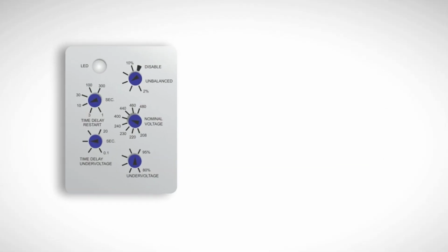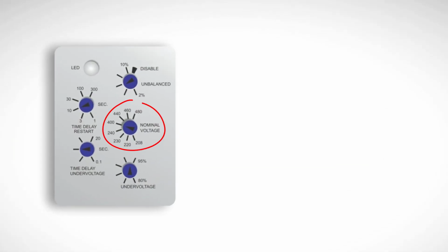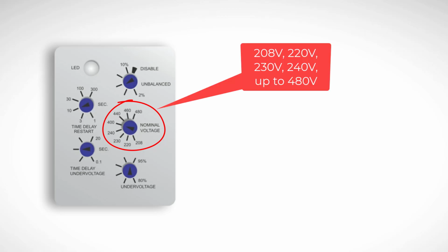This knob sets the nominal voltage. Options of 208, 220, 230, 240, up to 480 volts. You must match this to your system voltage. Wrong setting equals incorrect protection.